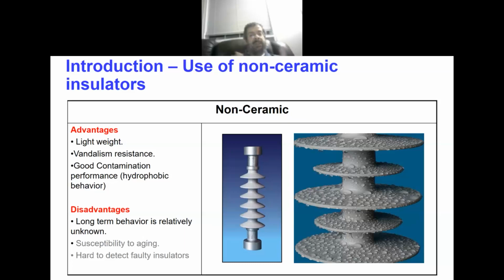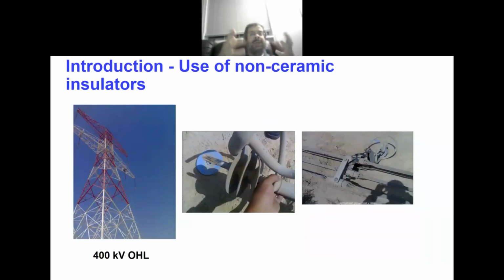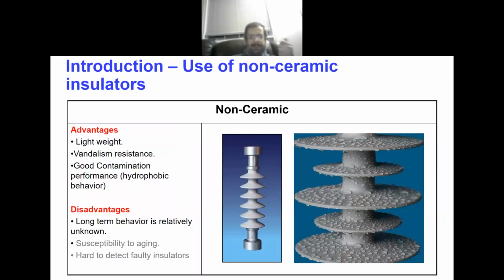The second advantage of these insulators is vandalism resistance. Ceramic or glass insulators are brittle, so if they fall on the ground at the site, they will be damaged. Non-ceramic insulators are made internally of a fiberglass core, encapsulated on the surface with silicone rubber material. So if they fall on the ground, the rubber absorbs the mechanical shock and they will not be damaged.